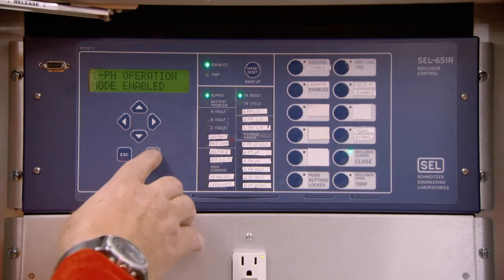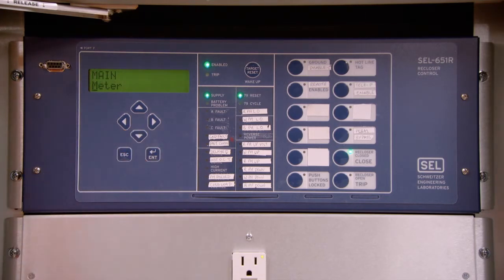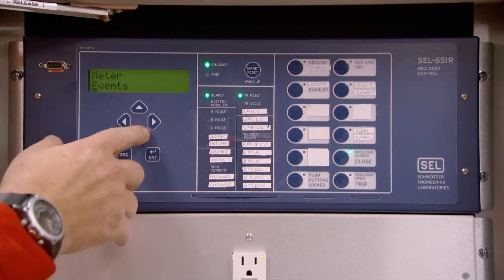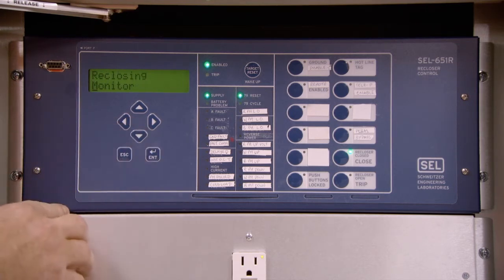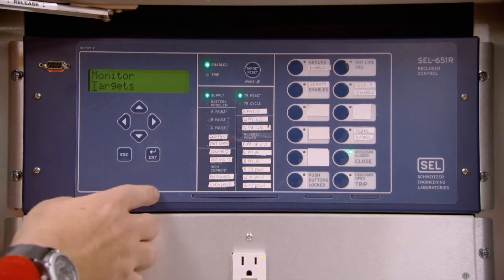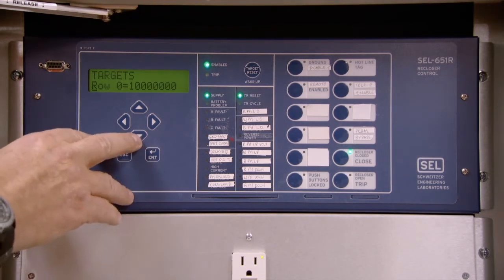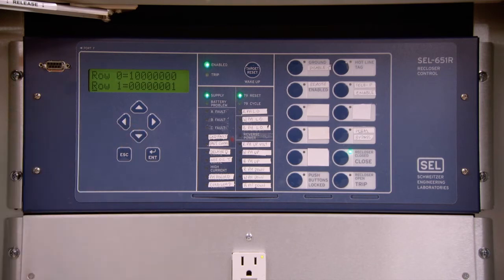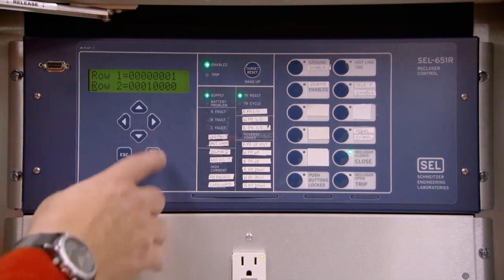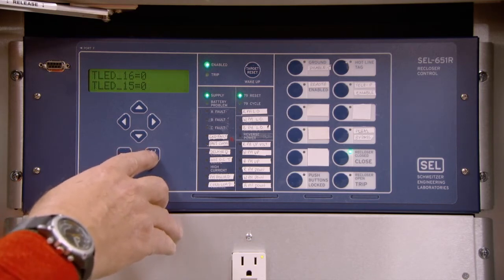Press Enter to access the meter screen. Now, using the down arrow key, scroll to Targets and press Enter. The row and target number are displayed. Using the down arrow again, we'll scroll to row 1. Referring to the reference manual will provide a target explanation in addition to what element has been picked up to trip this recloser. Press Enter to return to the scrolling screen.